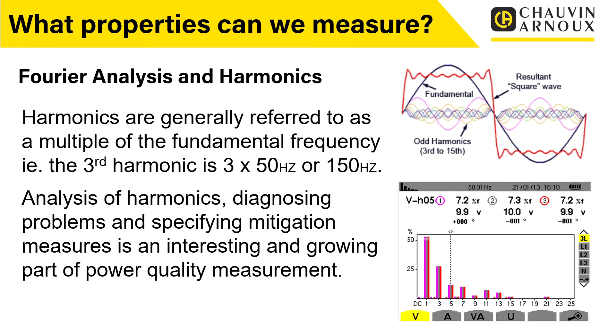Now, a simple way of specifying or measuring, quantifying, shall we say, harmonics is using this thing called total harmonic distortion, or THD. What THD does is it basically is a simple measurement that quantifies the amount of current or voltage harmonics present in a system. This value is a ratio of the current or voltage measured in the sum of all of the harmonics versus that measured at the fundamental. And this is often displayed as a percentage. So what we're saying is we've got a value of, say, voltage for the fundamental at 50 hertz. We add up all of the voltages at all of the other harmonics, and then we display it as a percentage. So what percentage is harmonic distortion versus the fundamental?